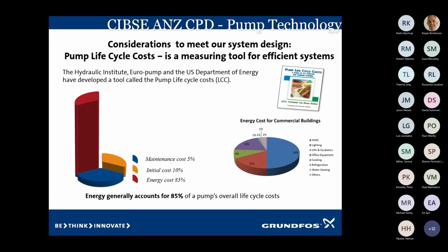The big consideration for any system that we look at is the life cycle cost. The initial outlay of the pump is only 15%. The total ownership of that pump, so if you own that pump for 15 to 20 years, the energy cost is the greater part by far. And I guess if we can have a look at that early, when we're selecting our pumps, we should take that into consideration.